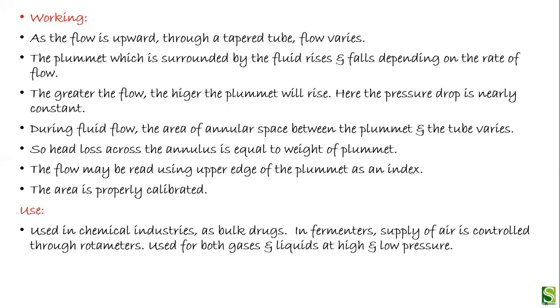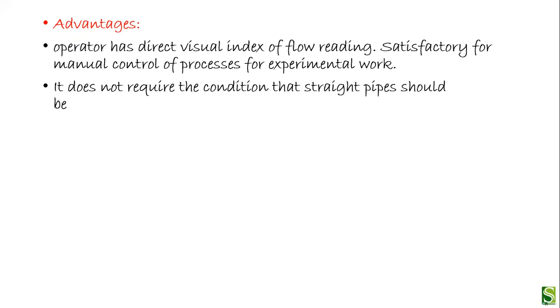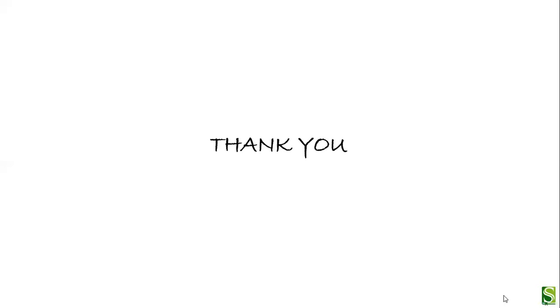The rotameter is used in chemical industries for bulk drugs. In fermenters, the supply of air is controlled through rotameters. It is used for both gases and liquids at high and low pressures. The advantage is that the operator has a direct visual index of the flow reading. It is satisfactory for manual control of processes and experimental work. It does not require the condition that a straight pipe should run before or after the flow meter. This was all about the equipment used for measuring the flow of any fluid.